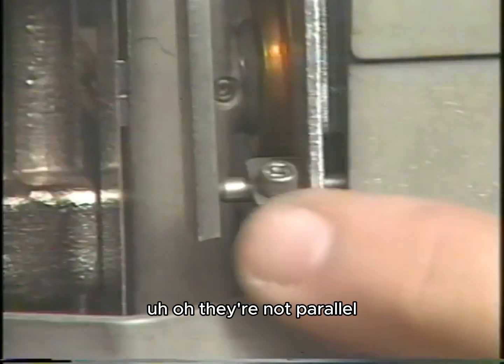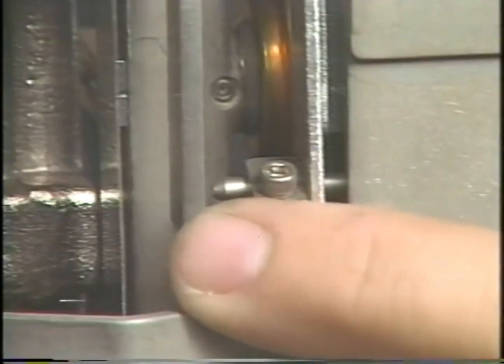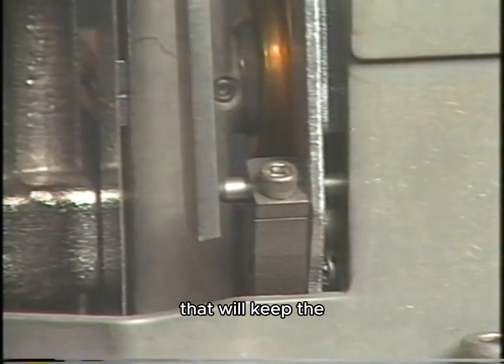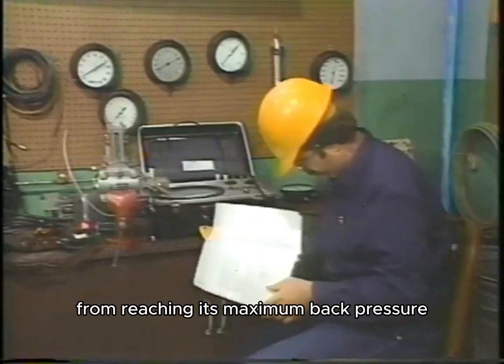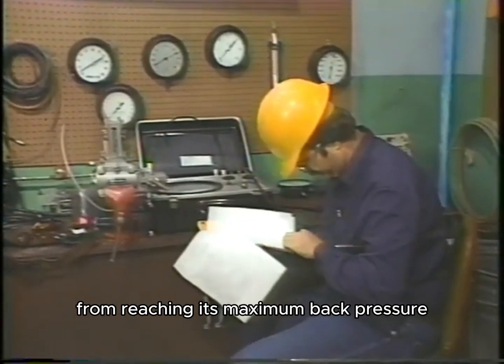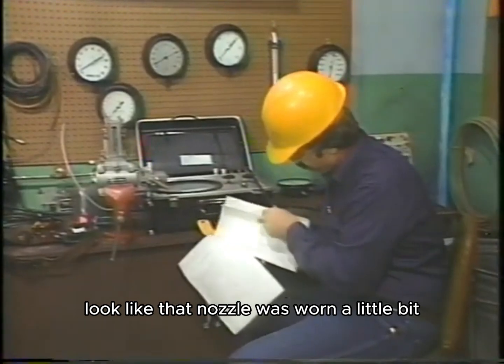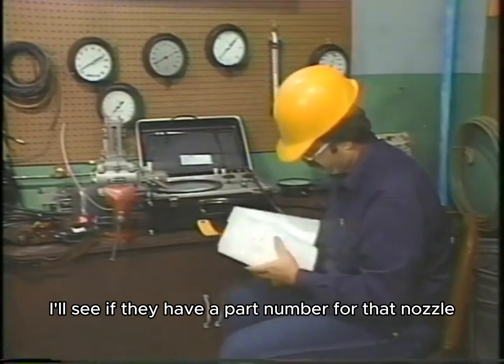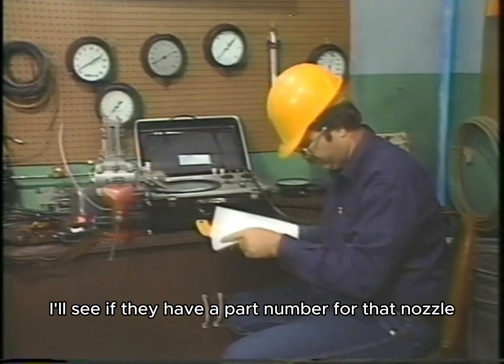Uh-oh, they're not parallel. Since they're not parallel, that'll keep the error detector in this transmitter from reaching its maximum back pressure. Looked like that nozzle was worn a little bit. I'll see if they have a part number for that nozzle.